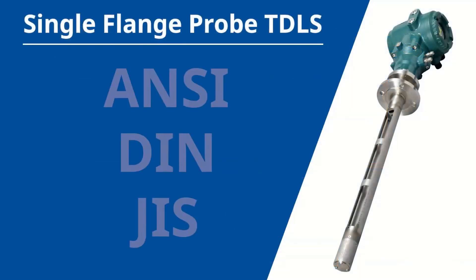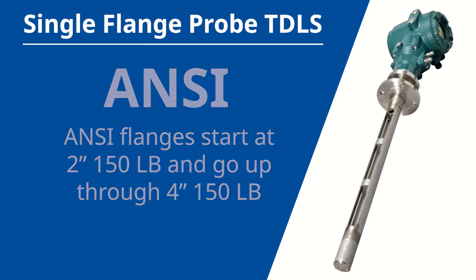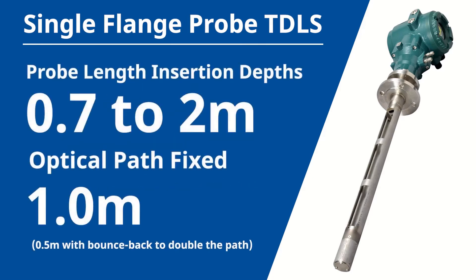The single-flange probe TDLS was built to accommodate a variety of standard ANSI, DIN, and JIS process flanges. ANSI flanges start at 2-inch 150-pound and go up through 4-inch 150-pound. Contact us if you have any alternative flange needs like 300-pound flanges. The probe lengths have variable insertion depths from 0.7 to 2 meters. The optical path is fixed at 1 meter — half a meter with bounce back to double the path.